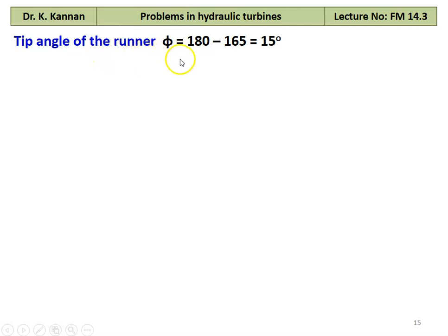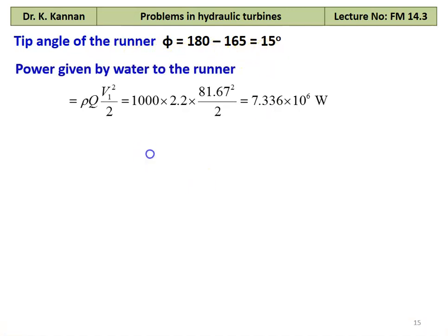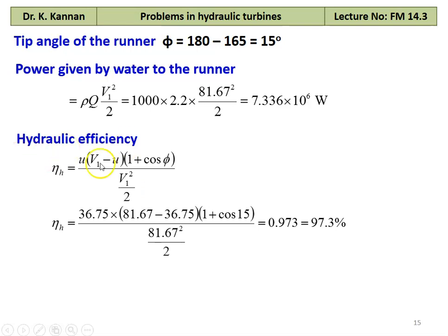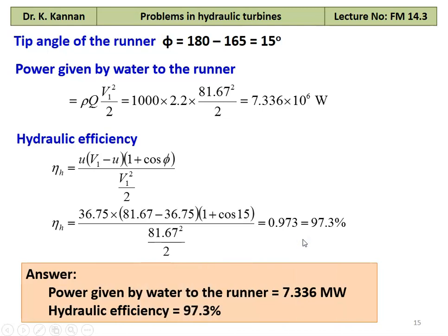Bucket tip angle φ = 180° − 165° = 15°. Power given by water to the runner = ρQ × V1²/2 = 1000 × 2.2 × 81.67² / 2 = 7.336 × 10⁶ W = 7.336 MW. Hydraulic efficiency ηH = U(V1 − U)(1 + cos φ) / (V1²/2) = 36.75 × (81.67 − 36.75) × (1 + cos 15°) / (81.67²/2) = 0.973 = 97.3%. Answer: Power = 7.336 MW, hydraulic efficiency = 97.3%.